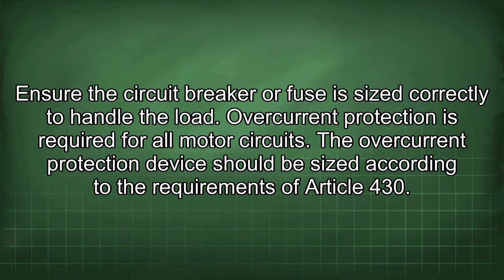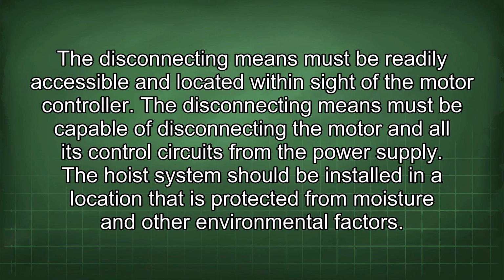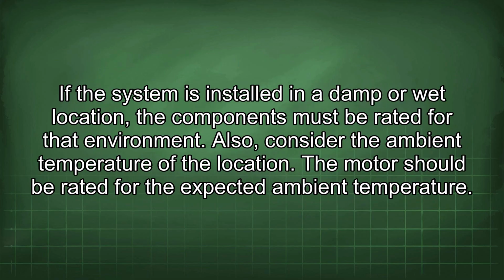The overcurrent protection device should be sized according to the requirements of Article 430. The disconnecting means must be readily accessible and located within sight of the motor controller. The disconnecting means must be capable of disconnecting the motor and all its control circuits from the power supply. The hoist system should be installed in a location that is protected from moisture and other environmental factors. If the system is installed in a damp or wet location, the components must be rated for the environment.